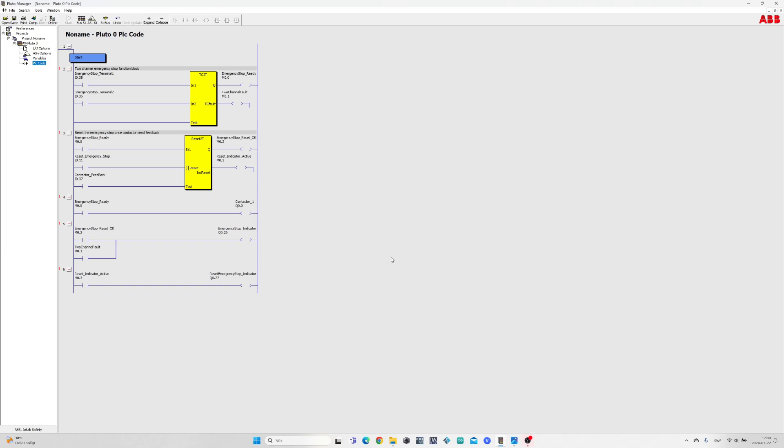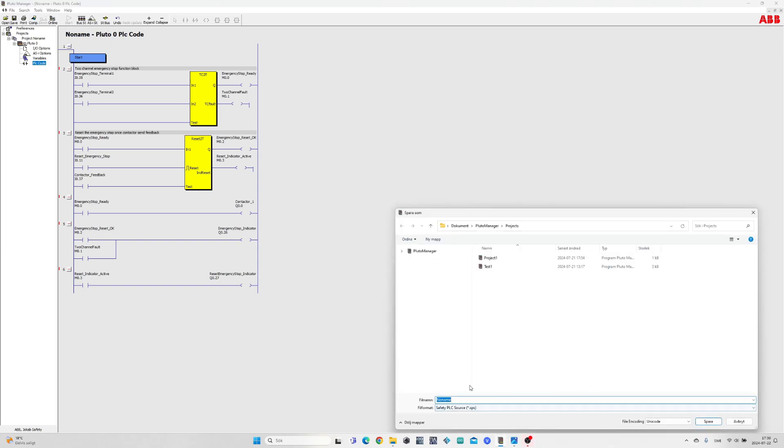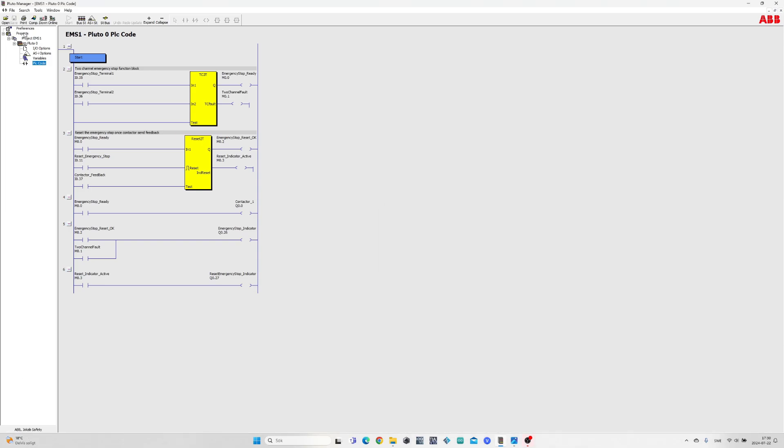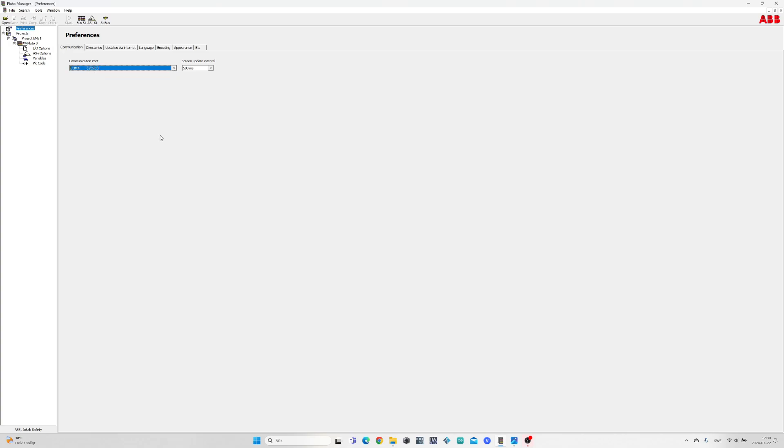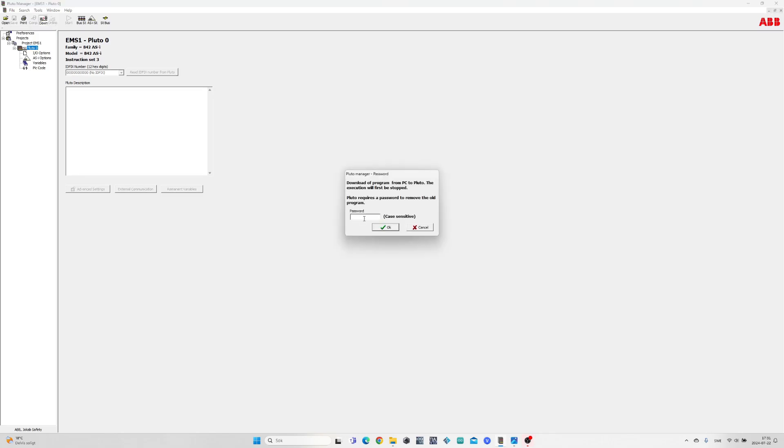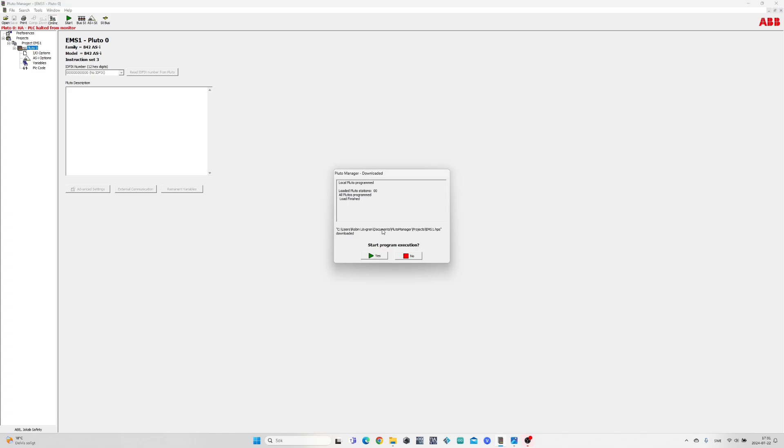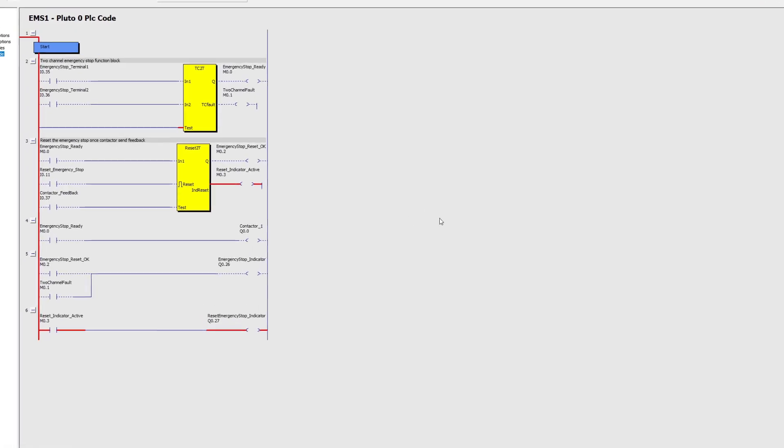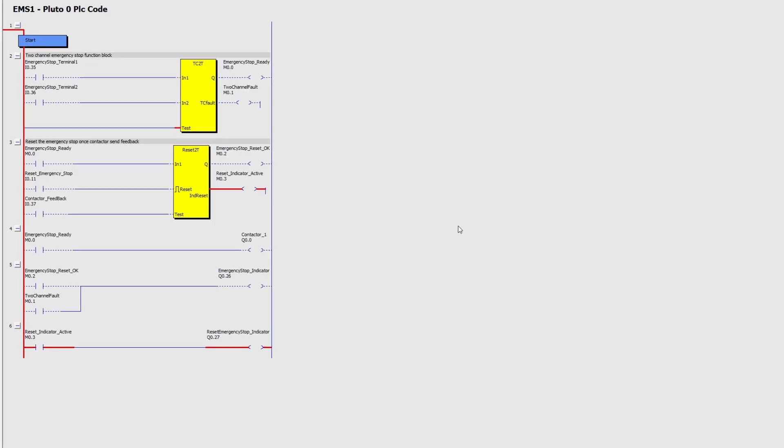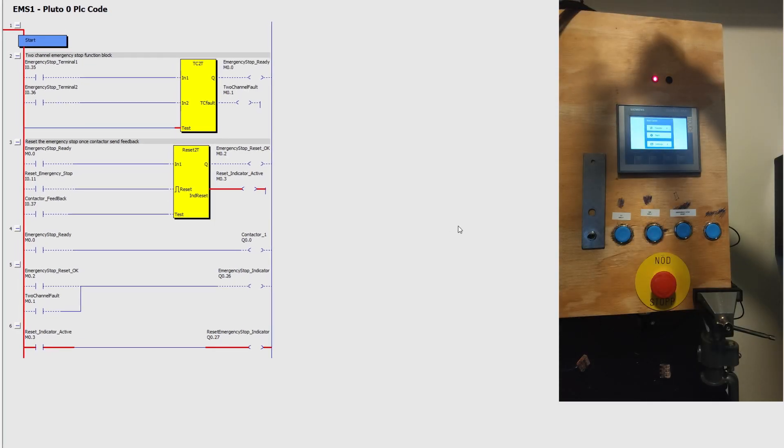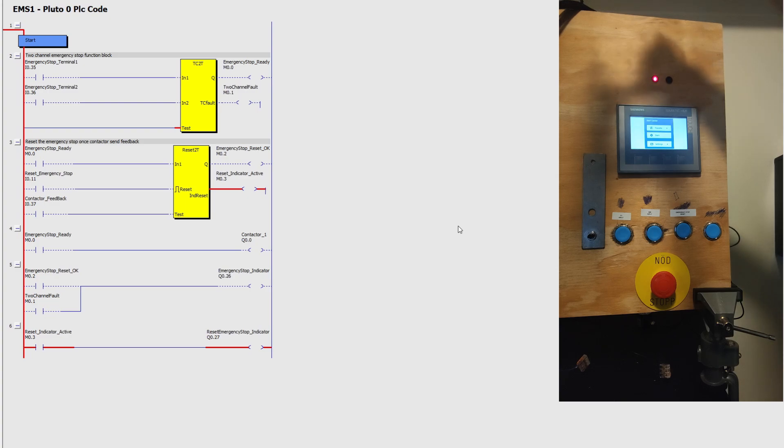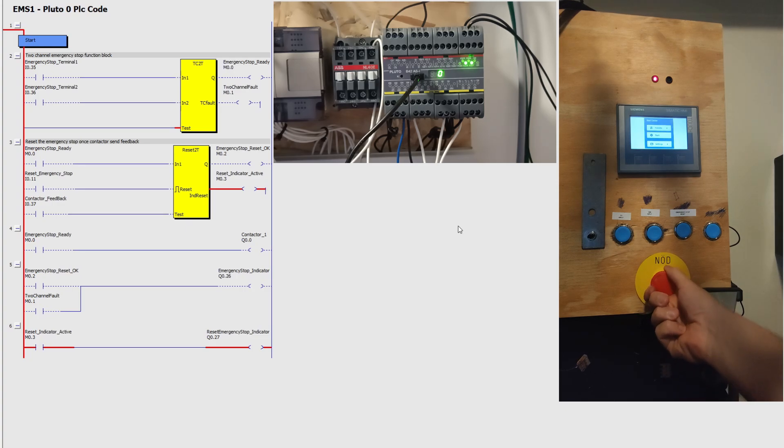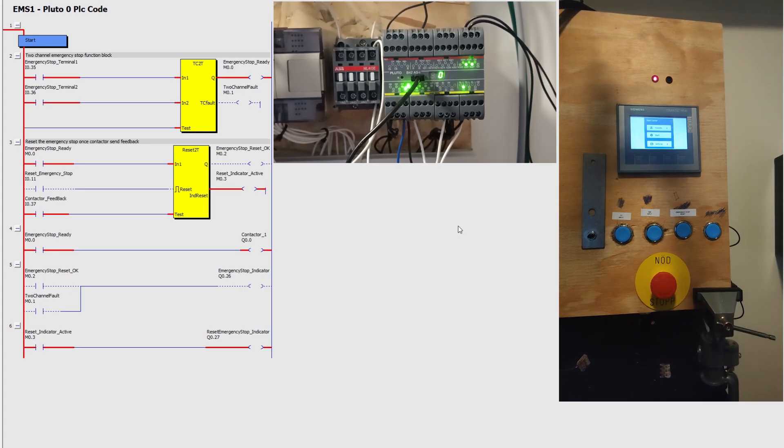I will now download the program to the PLC and test it out. My emergency stop button is pressed now then my LED indicator will be active at all time and my contactor won't be active. But if I release it the contactor will trigger and the red indicator will be pulsing. This indicates that I can reset it with my button.